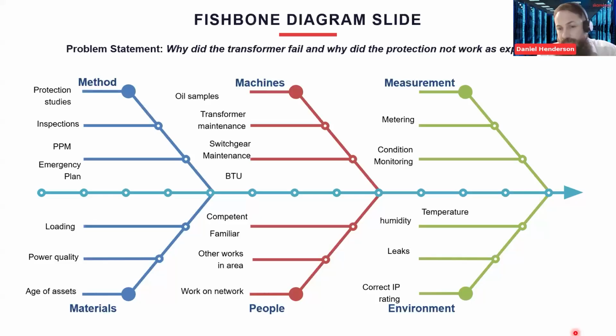Leaks, I'm not sure. I like to think nothing got into the box from outside, with it being compound filled. But because you can't remove the cover, they can't really verify that. And maybe something from in to out, so maybe oil coming through the bushings. I'm not sure, but there are no indications externally. And IP rating, again, that probably was quite verified with it being a compound filled box. Anything to add on there?